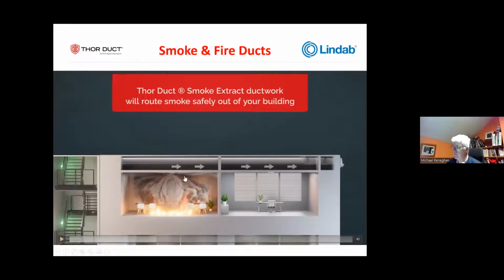So here's the first scenario, a smoke evacuation system. The idea of your duct is that it will pull the smoke from the scene of the fire, and it needs to do it safely through another compartment and throw it outside. So this compartment is protected by having an EI rated product to the rating of the compartment. Again, it's taking the hot gases and preventing fire from breaking out here while the fire is ongoing.